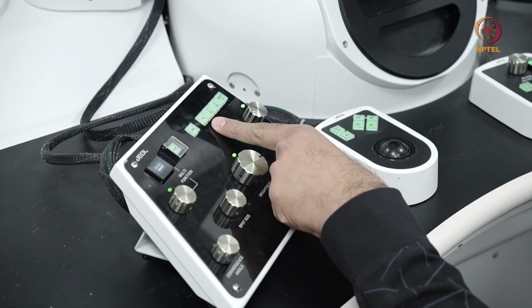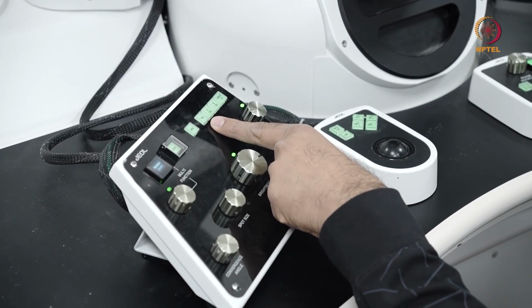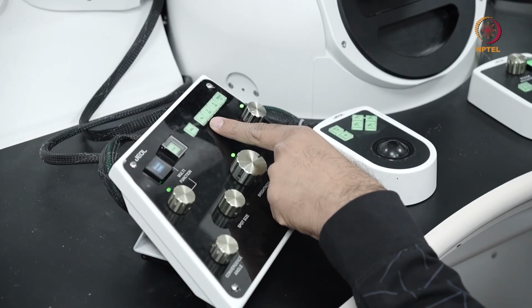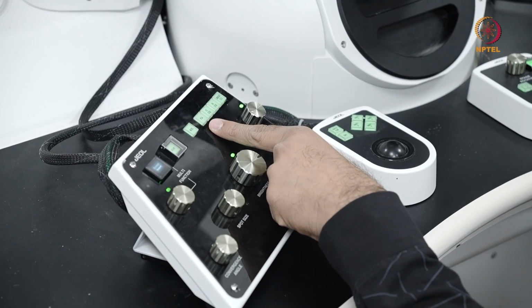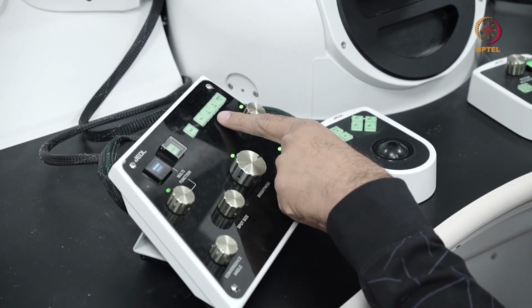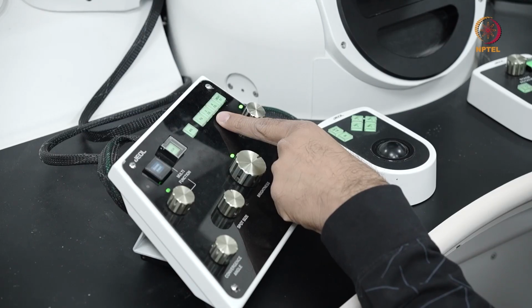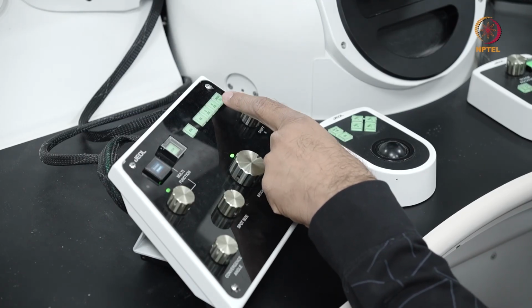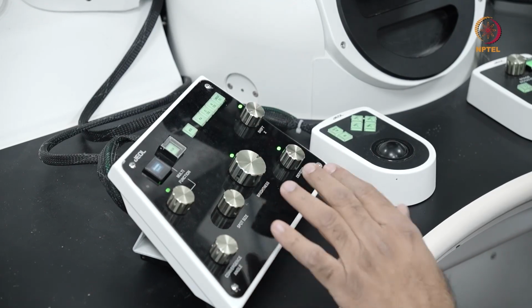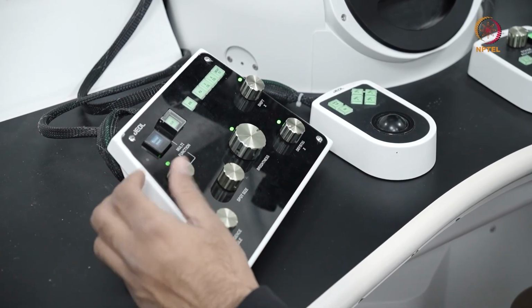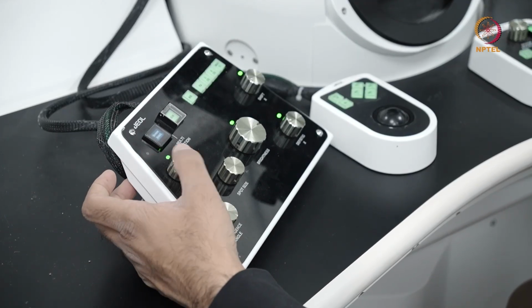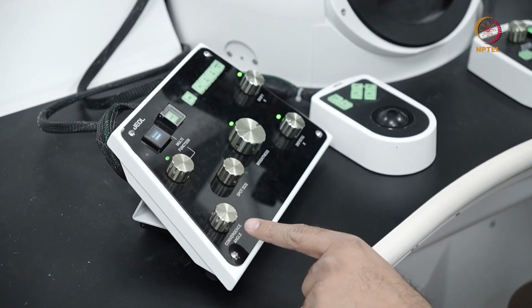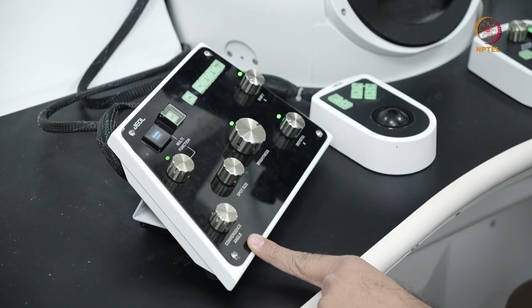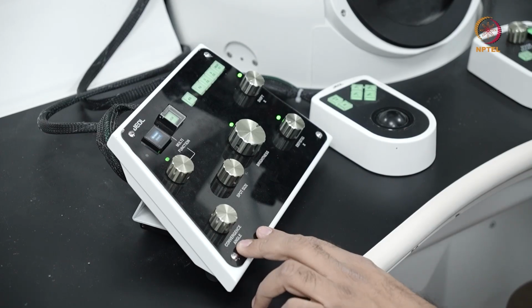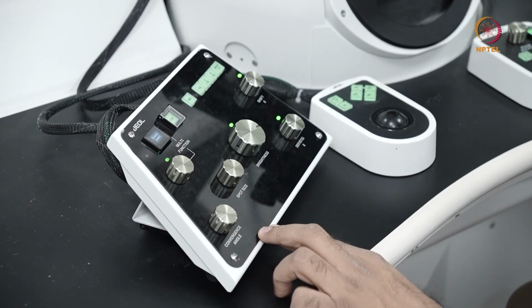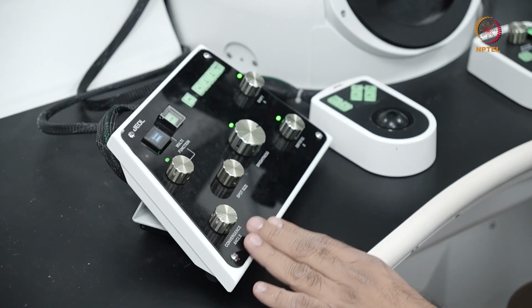The PLA button is again for using to do the diffraction shift, or when you're imaging in STEM mode to move the STEM signal that you get, the forward scattered electron signal, to the center of the detector. You have the condenser lens stigmation correction here, the objective lens stigmation correction, and you have the beam tilt button here. The knobs, if you see, you can assign different values to the multifunction knobs, and this is to make it coarser or finer. You have something to choose the convergence angle. In the other instrument, you had spot size and convergence angle as alpha, where you could select from alpha 1, 2 and 3. Even here it is similar, you can choose the alpha or the convergence angle here.